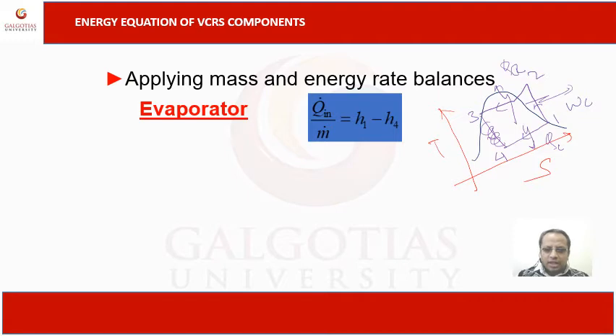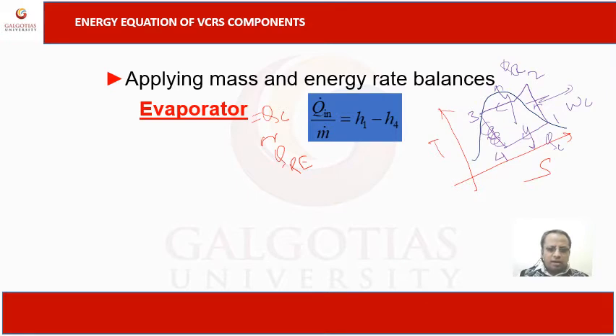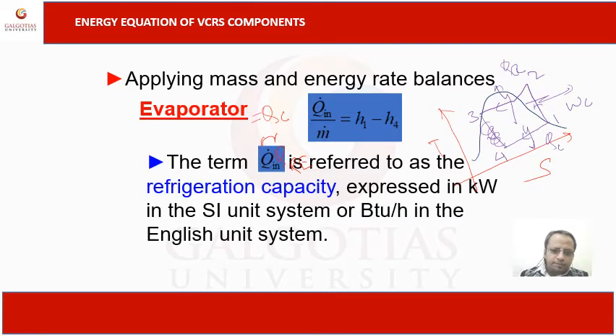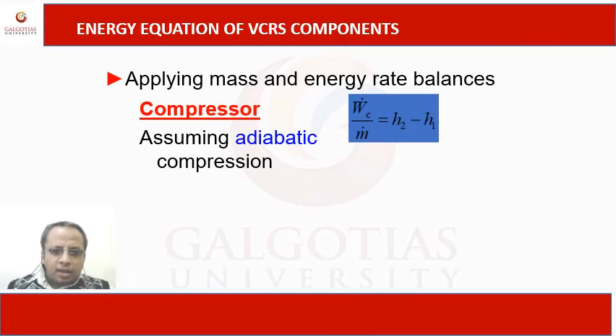The enthalpy change H1 minus H4 gives the cooling effect — we can write Q_cooling or Q_refrigeration effect equals H1 minus H4. Following the refrigerant vapor table, we can find all enthalpy values as per the temperature and pressure given in a practice question. This equation gives the refrigeration effect. Q is referred to as the refrigeration capacity and is expressed in kilowatts in SI units and British thermal units per hour in the English unit system.